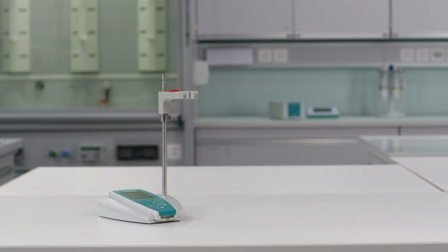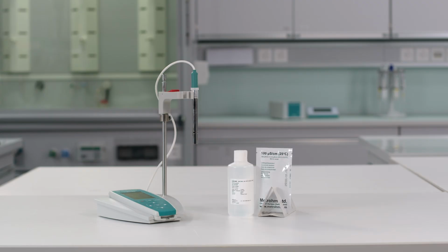For routine use in stable conditions, calibration might be checked weekly, monthly, or as required by your internal quality procedures or regulatory standards. For the calibration, you need your conductivity meter, the conductivity measuring cell, certified conductivity standards, and deionized water for rinsing. Only use fresh, certified conductivity standards.